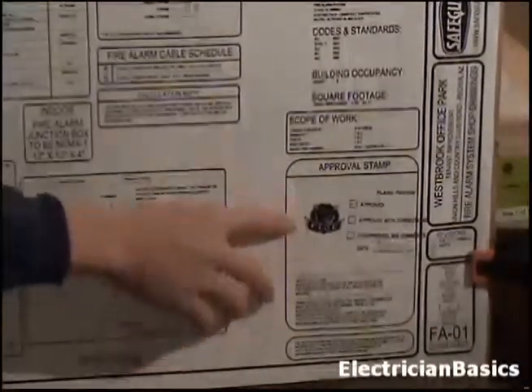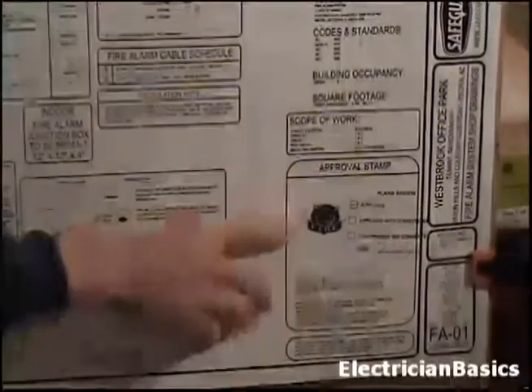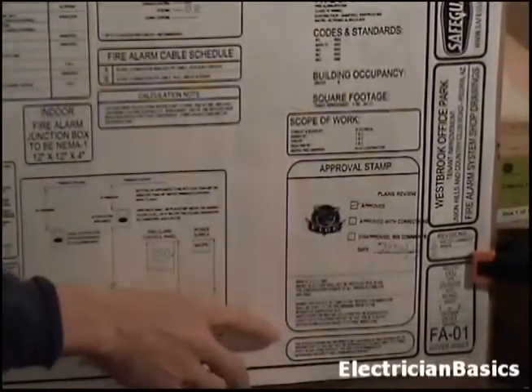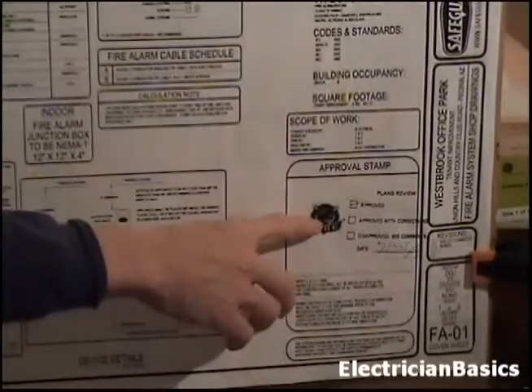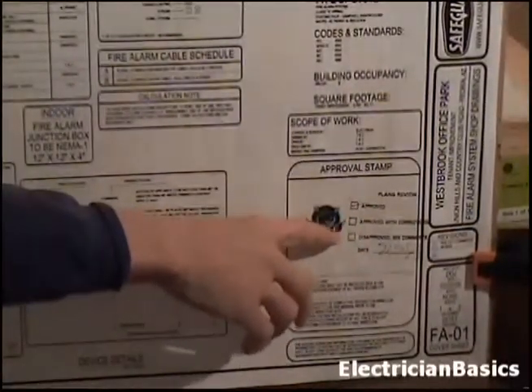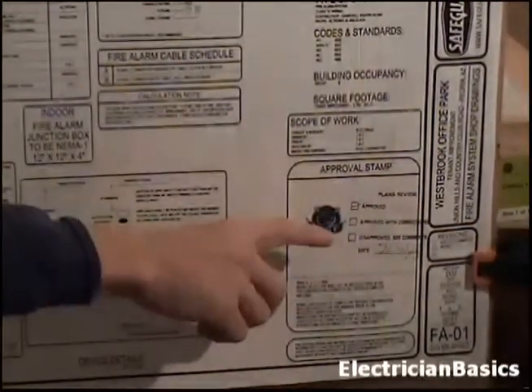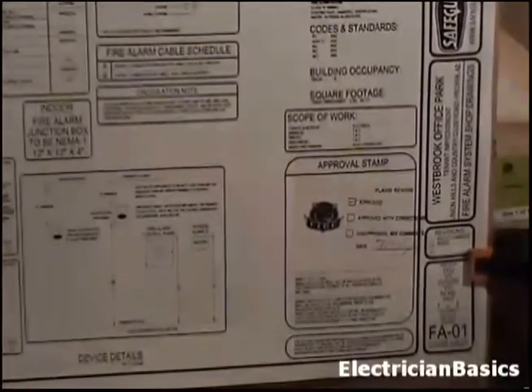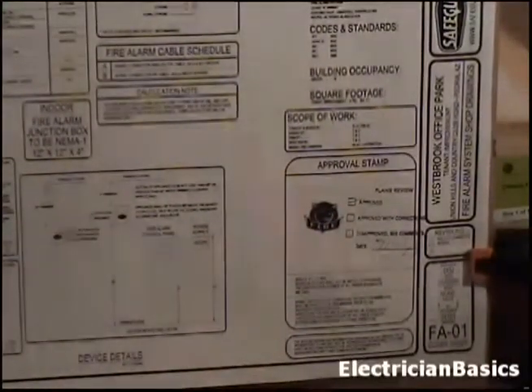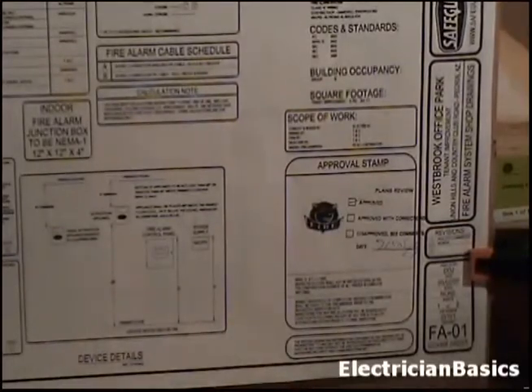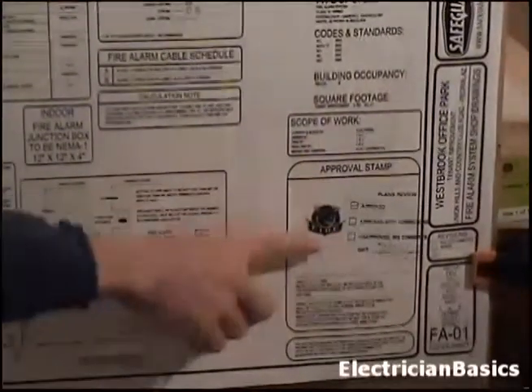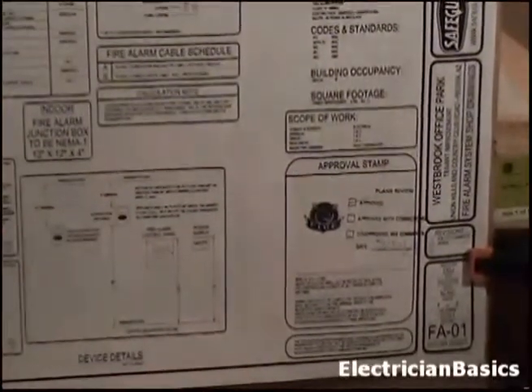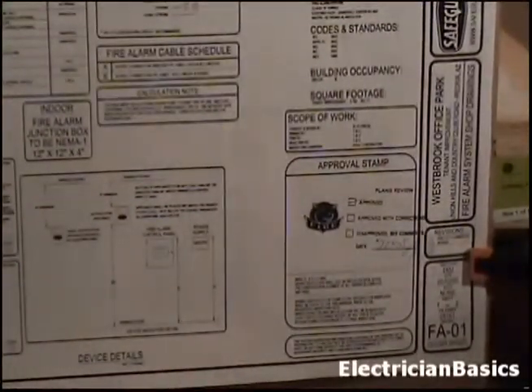Even though, well, this was put in, it is kind of a standard thing in one sense, but to get the stamp with these check marks, that is something that is stamped on, and again the fire marshal has to approve that. And of course, anytime during the construction, if they don't think you're putting this system in properly, they can move you from approved down to disapproved. So keep this in mind. This is not a place where you want to be taking any shortcuts whatsoever.